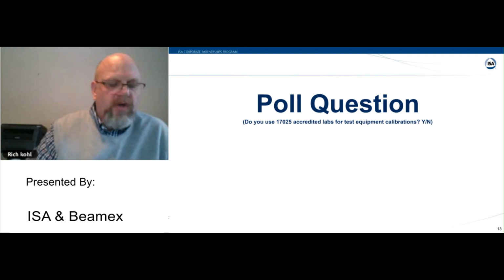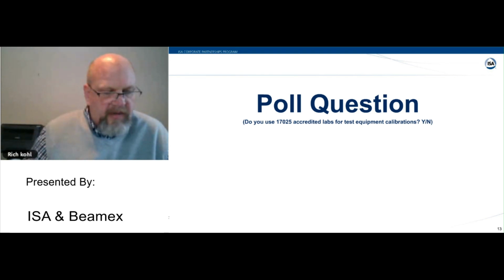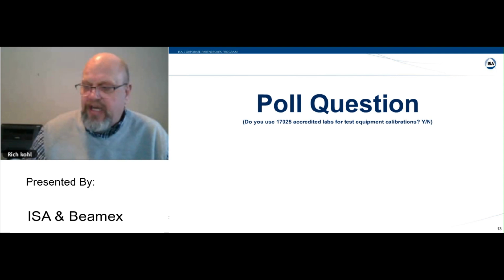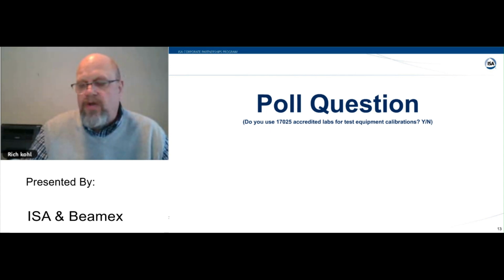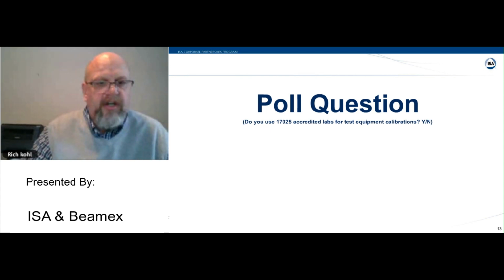So I just want to make a quick note, before we go on, about expanded uncertainty that Ned was just talking about. This is very important. You'll see this listed on your spec sheets and your calibration certificates as K equals 2. It's important to take note of this because contributing factors that are going to be combined to get your total error or total uncertainty all have to be expanded to the same K-factor in order for you to perform the math to bring them together. So that's just something to watch out for later.